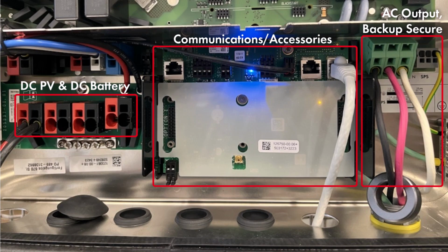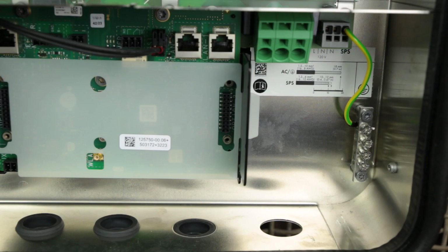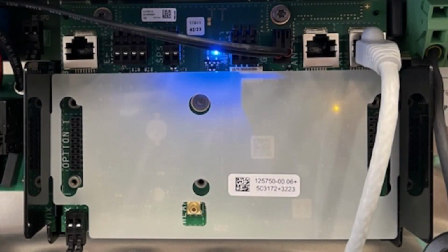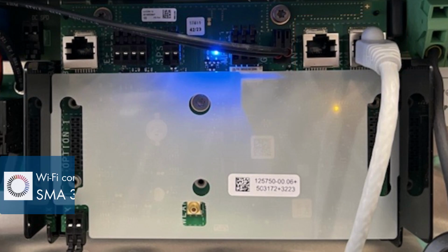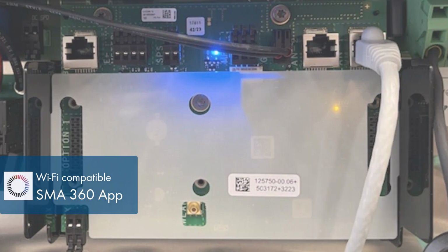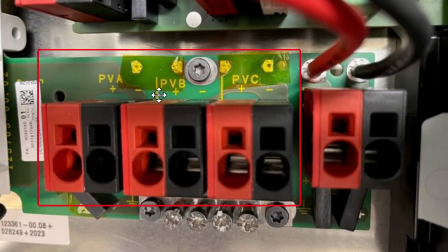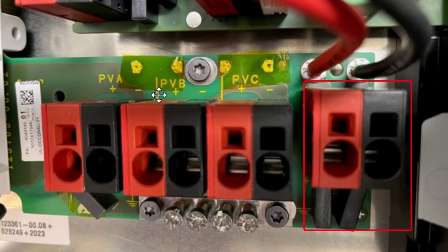Here's a quick overview of the wiring area. On the bottom right, you'll find the AC terminals, the ground bus bar, and the backup secure terminals. Slightly to the left of the AC terminals, you have the communication ports with labels. You may also connect to the homeowner's Wi-Fi using the 360 app. And to the bottom left, you have the DC PV terminals with appropriate labels, while the far right terminals are for the DC battery.